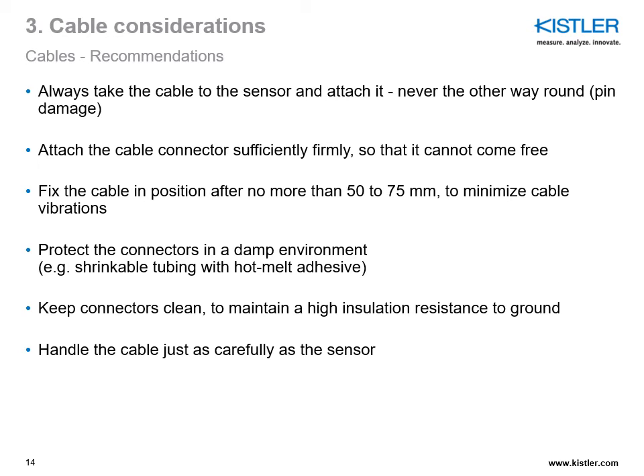Never attach the cable the other way around, to avoid any pin damage. Attach the cable connector sufficiently firmly so that it cannot come free during the measurement. It's recommended to fix the cable in position after no more than 50 or 75 mm of cable length, to minimize cable vibration. Whenever you have a damp environment, always use some protection on the connector like shrink tubing. Always keep connectors clean to maintain high insulation resistance to ground, especially for charge output sensors. And handle the cable just as carefully as the sensor.